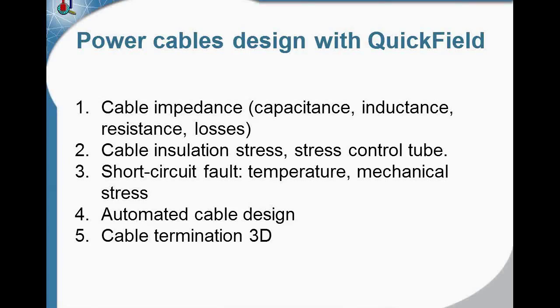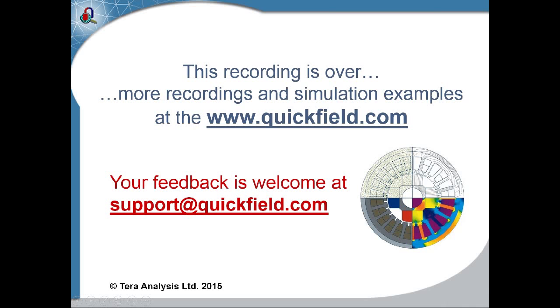And we simulated the case of the cable termination with the stress control tube and saw the effects of the stress control tube on the electric field stress distribution. And we also simulated the cable with the automated cable design tool that was implemented in the Microsoft Word document. And the last example was the cable termination three-dimensional example.